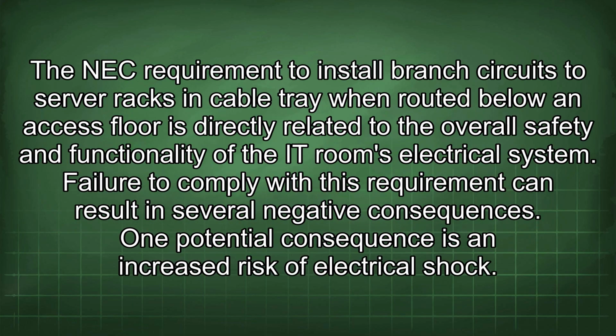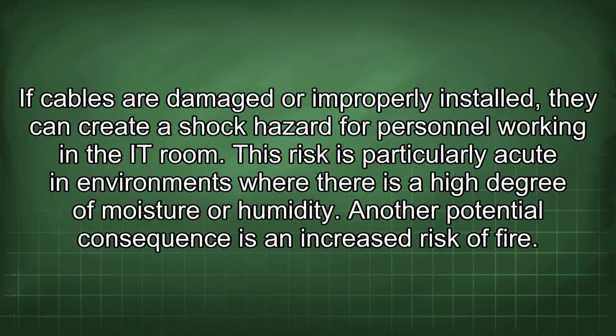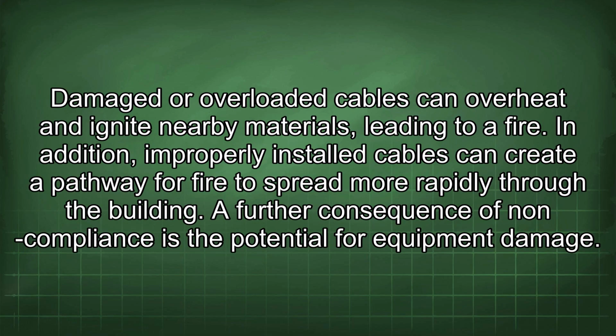The NEC requirement to install branch circuits to server racks in cable tray when routed below an access floor is directly related to the overall safety and functionality of the IT room's electrical system. Failure to comply with this requirement can result in several negative consequences. One potential consequence is an increased risk of electrical shock. If cables are damaged or improperly installed, they can create a shock hazard for personnel working in the IT room. This risk is particularly acute in environments where there is a high degree of moisture or humidity. Another potential consequence is an increased risk of fire. Damaged or overloaded cables can overheat and ignite nearby materials, leading to a fire. In addition, improperly installed cables can create a pathway for fire to spread more rapidly through the building.